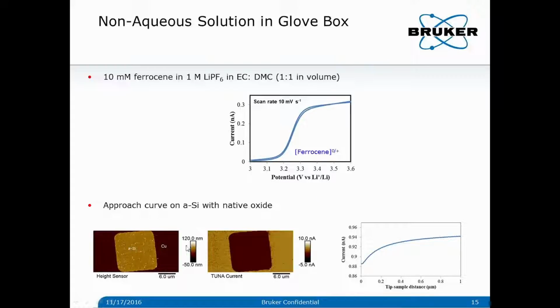And here is a conductive AFM image of a silicon anode pattern on a copper current collector. This measurement was done using the SECM nanoelectrode probe as a conductive AFM probe inside a glovebox, in a dry environment, no liquid here. I just want to show you that on an amorphous silicon surface, because of the native oxide, you won't see any electrical current. We know that this oxide surface is inactive. So we use the same sample and run the feedback mode of the SECM in this solution with the ferrocene, and you can see that we get an approach curve, and the negative feedback is as expected on the silicon surface because this is inactive.